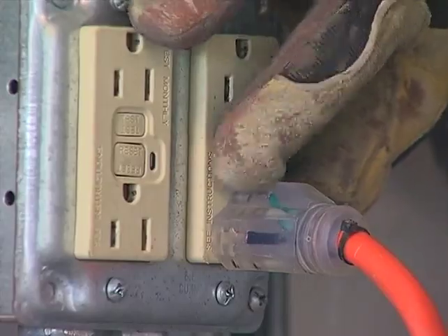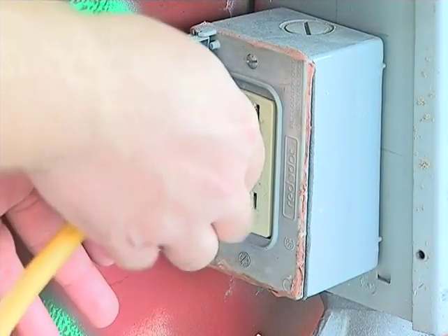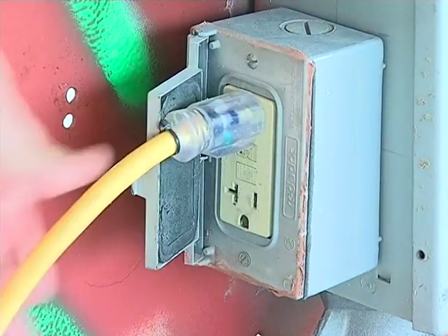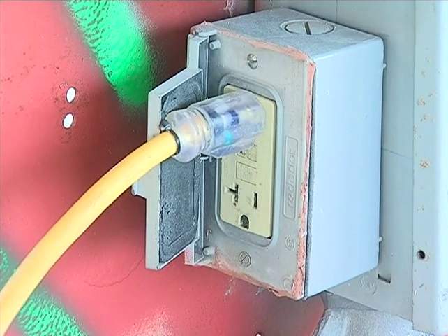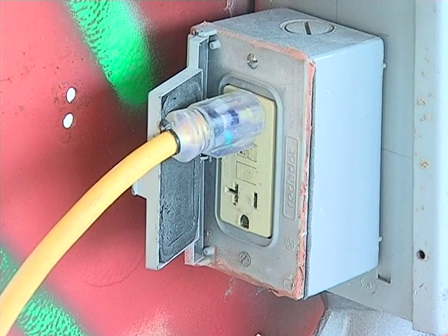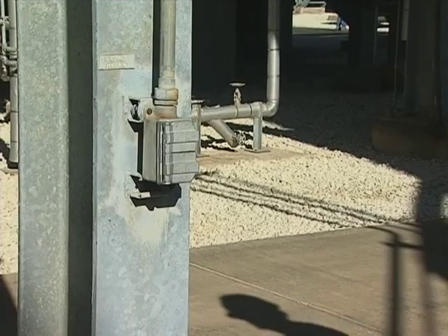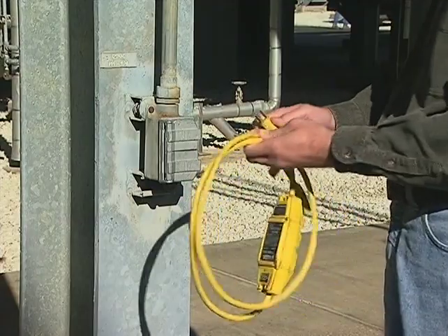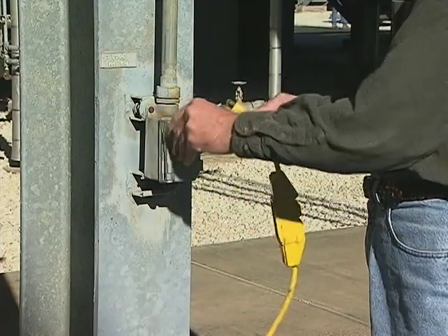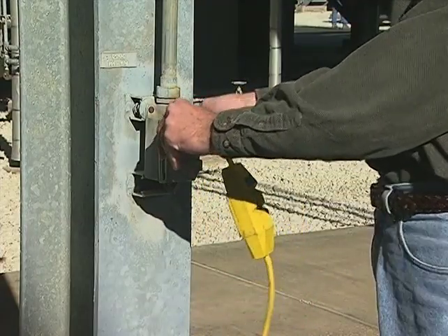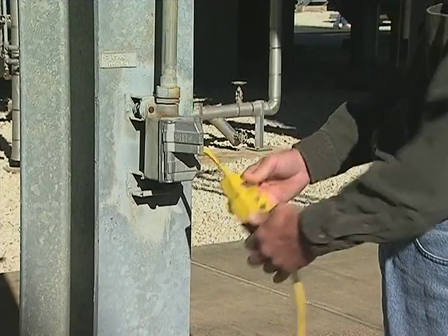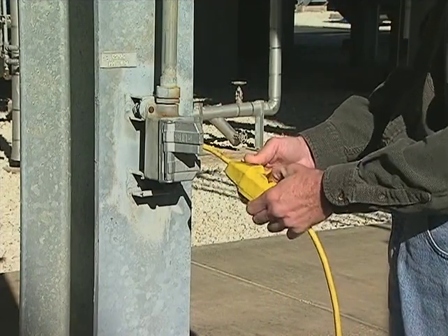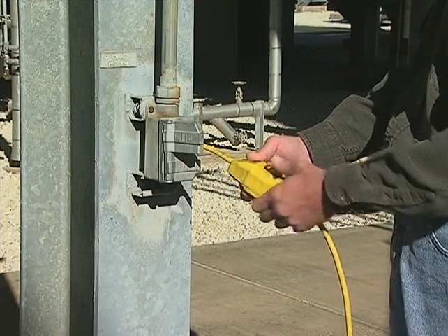by workers. If a receptacle or receptacles are installed as part of the permanent wiring of the building or structure and they are used for temporary electrical power, GFCI protection shall be provided. Receptacles on the ends of extension cords are not part of the permanent wiring, and therefore the cord's receptacle must be of the GFCI type, whether or not the extension cord is plugged into permanent wiring.